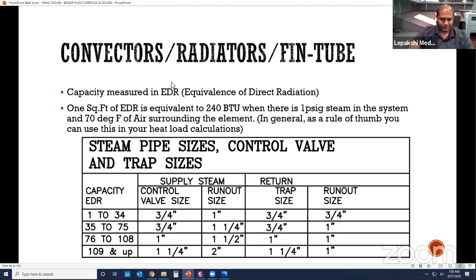And the sizes are over here. How are you going to come up with this? The capacities are measured in EDRs. That's the term they normally use for convectors. EDR is the short form of equivalent direct radiation. For every 1 square foot of EDR, you have to have 240 BTUs. And these are the steam traps.